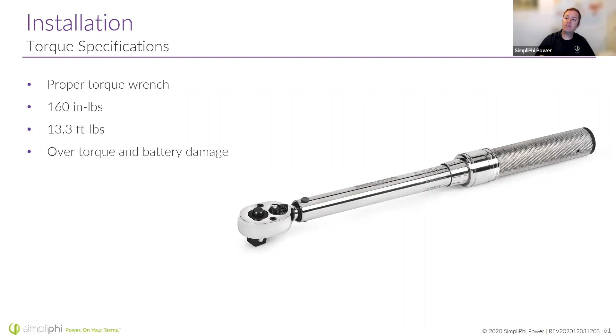We want to see 160 inch-pounds on those battery terminals. The last thing I want to see is one of your technicians out there with an impact driver going to town on one of these battery lugs and snapping it off. Maybe your torque wrench should be an insulated tool. But remember, the batteries have a built-in breaker, so you can turn that breaker off and make those battery leads go dead, so you're not worried about arcing and getting a big pop.